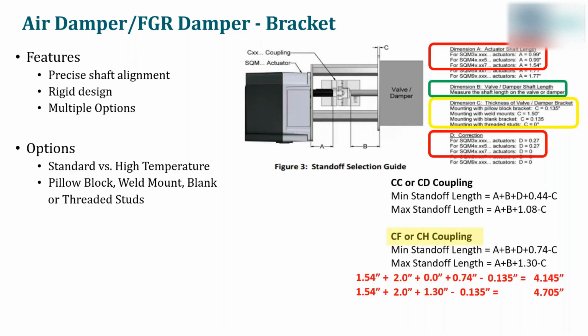Now, one of the things that we need to do is size the bracket. In this example, we're going to assume that we're using an SQM48 with a pillow block bracket. So if you look at the dimensions on here, dimension A refers to the actuator shaft length. Since we're using SQM48, that dimension is 1.54 inches. Dimension B is the valve damper shaft length. We will assume it's 2 inches.